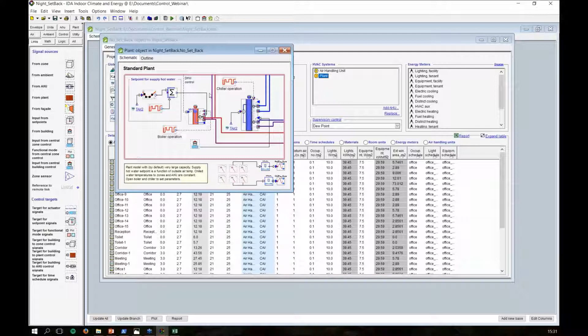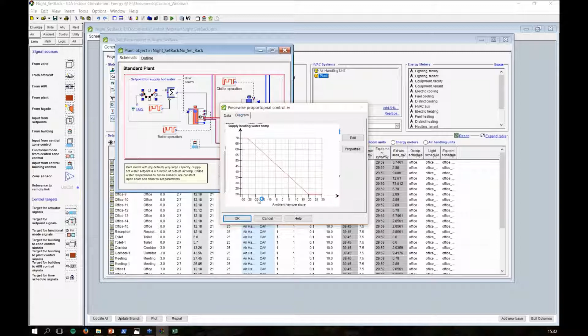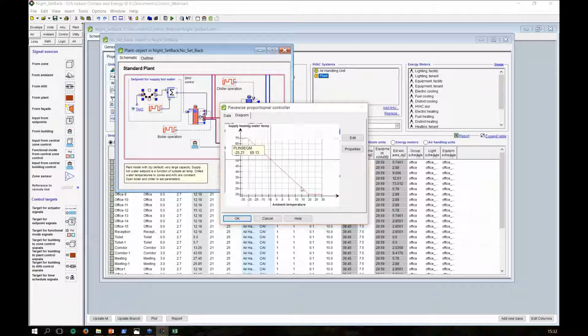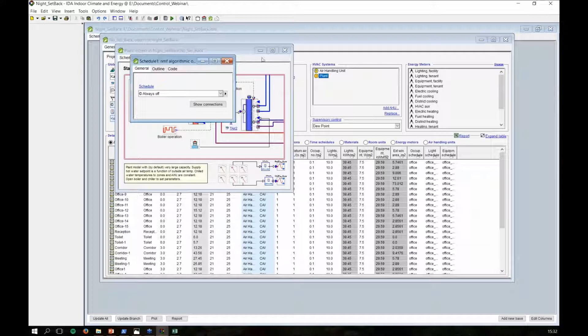Night setback. For night setback, I wanted to show several cases. The first one doesn't have a night setback. Let's open that and start with that. So here we have a plant, and for the boiler, you have an option in IDA ICE by default to put a setback schedule. So you're trying to control the set point temperature based on outside temperature. That's T-air2, the outside temperature, and you have some linear controller here. If I open this, you'll see that as outside temperature drops to -25, we want our set point to be 70, and then it goes proportionally down to a minimum of 20. And then you have an option of putting a schedule. I'm going to create a case where I don't have anything, so always off, the first one.